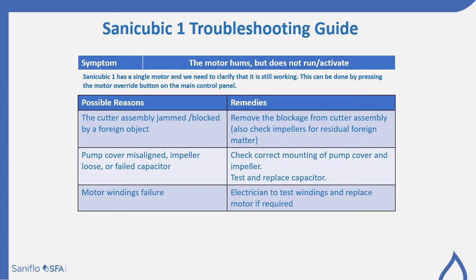You might find that the motor is humming but does not actually run or activate. So generally find here that the cutter assemblies, the grinder section, may have been jammed. It could have been blocked by a foreign object. Remove the blockage from any of those cutter assemblies, but also check the impellers for any residual foreign matter.